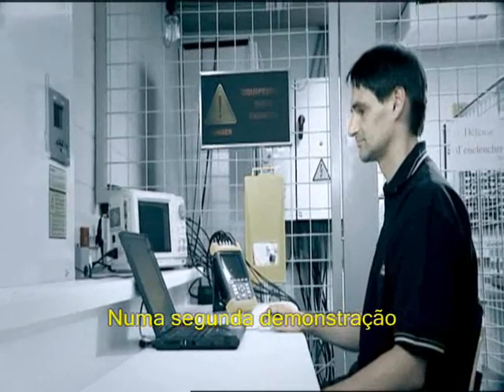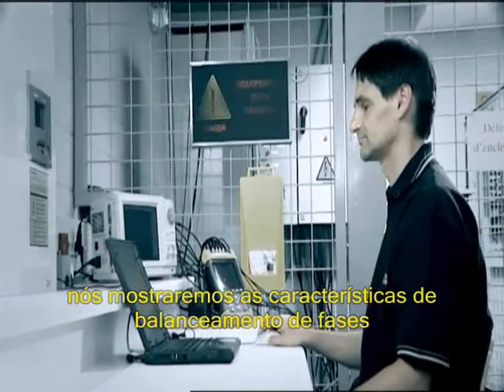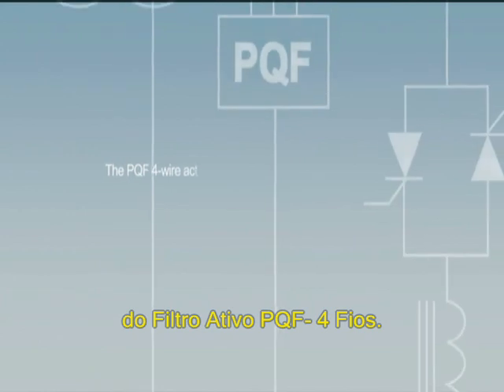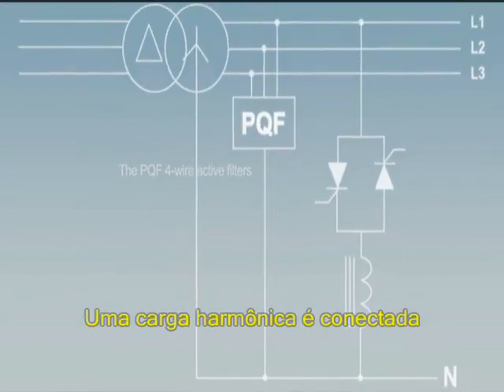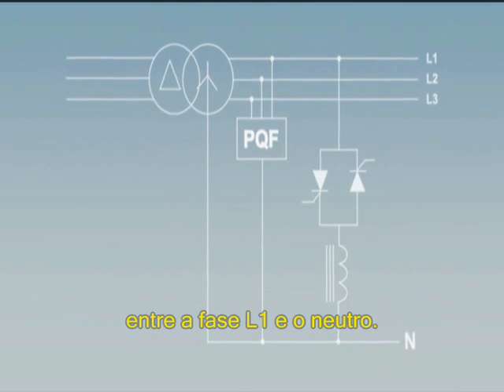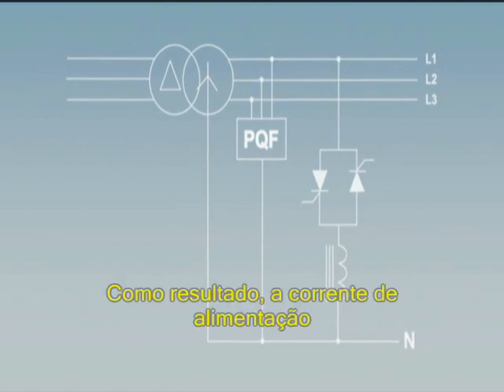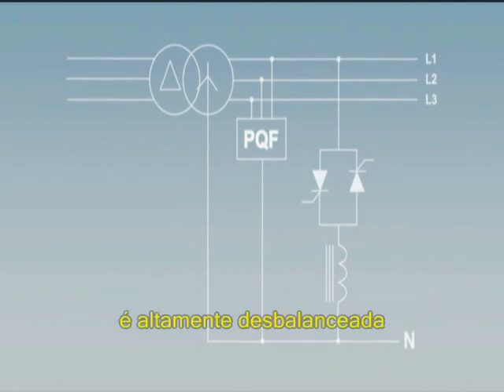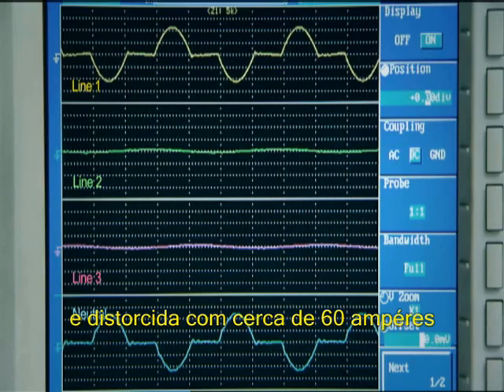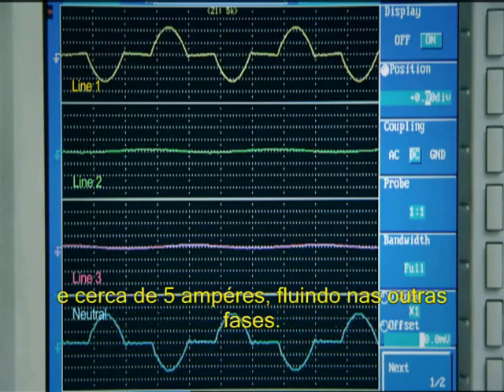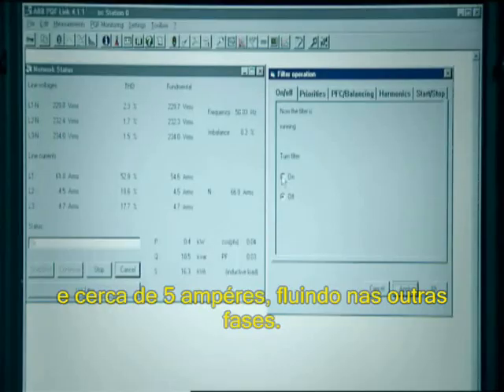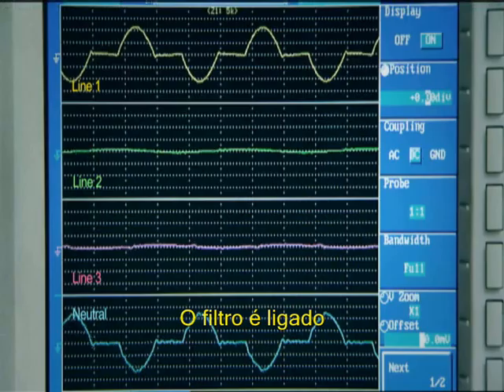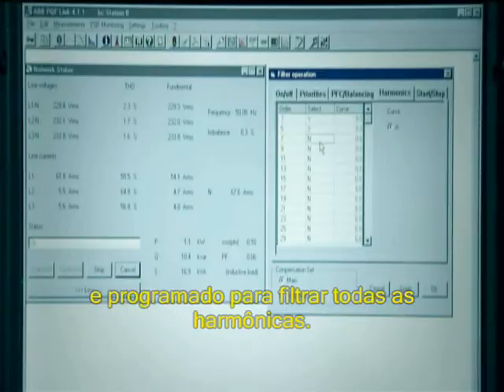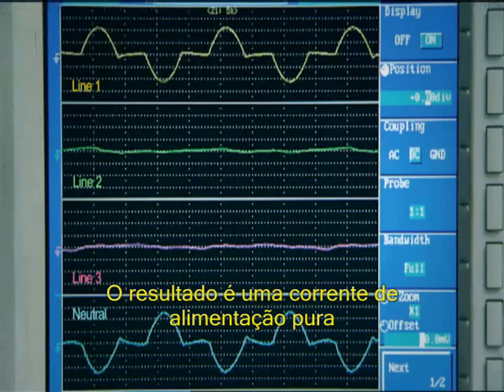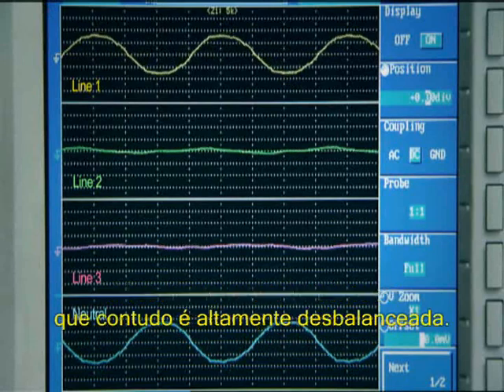In a second demonstration, we will now show the load balancing features of the PQF 4-wire active filters. A single-phase harmonic load is connected between line 1 and the neutral. As a result, the supply current is highly unbalanced and distorted, with about 60 amperes flowing in line 1 and the neutral, and about 5 amperes flowing in the other lines. The filter is then switched on and is programmed to filter all the harmonics. The result is a clean supply current, which however is still highly unbalanced.